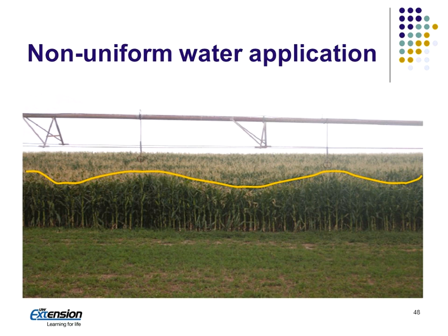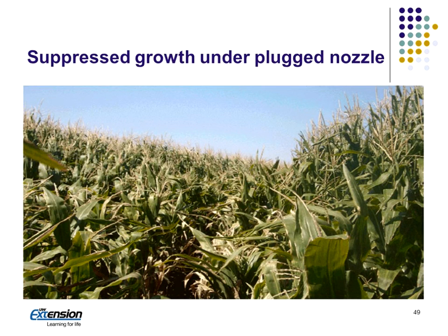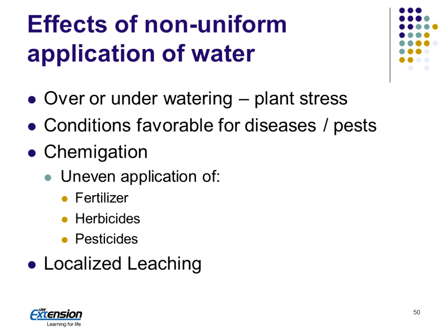The other thing we can identify, and this would be on a commissioning type test, is an example of here's one nozzle here and one nozzle there. They're probably either not the right nozzle or the pressure's been reduced because we're getting water deficit in between the nozzles. So it's an example of that it's not designed right, or there's been a change in the system. So that's the kind of problem that it'll find. Here's an example of a plugged nozzle. So you get this little valley underneath. What this test won't necessarily do is pick up spoking that I talked about earlier because of the way we're going to test. But it does look for over or under watering.